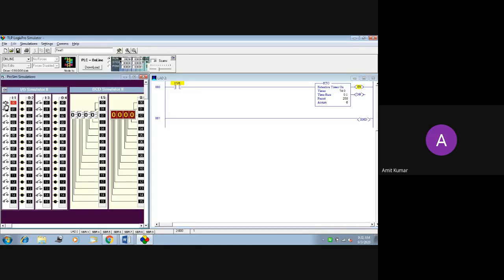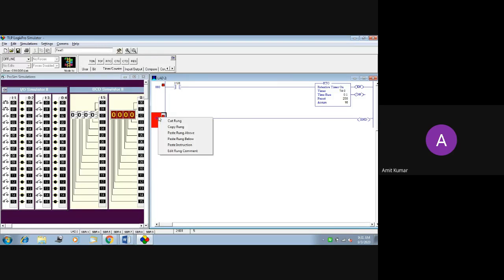If you run this here, now I have reached up to 16 and by mistake I have released the rung. Now you can see the accumulator value here is 16. It has not become 0, the retentive timer has not reset. So where you need to hold the values of your timer, there you can use the retentive timer. But there is again a limitation of the retentive timer. This timer cannot be reset by itself. So you need to reset the timer using the reset function.